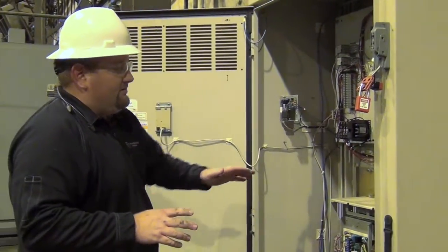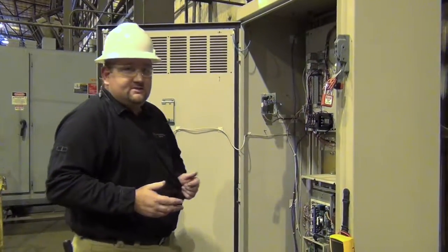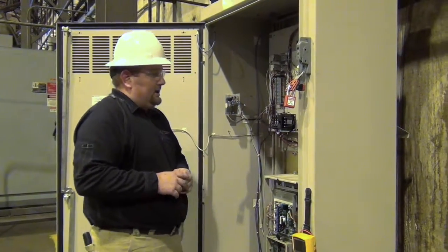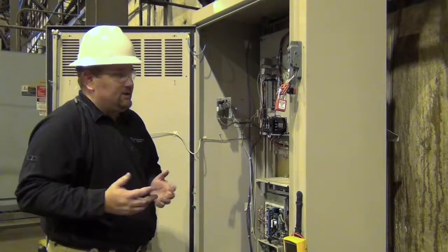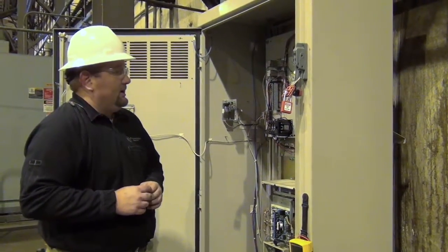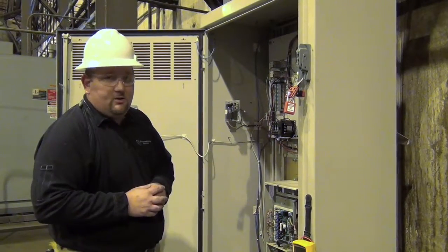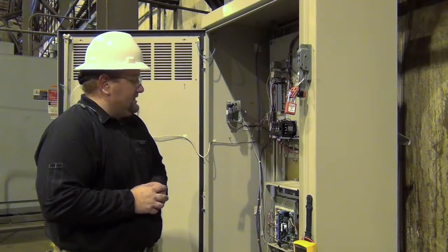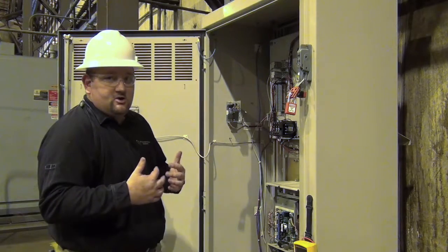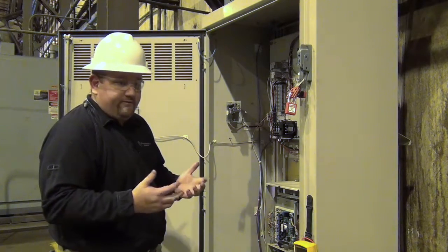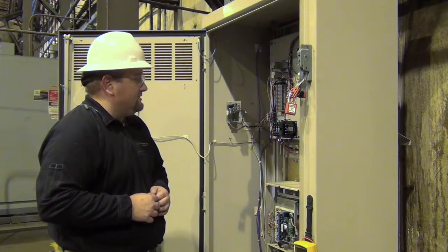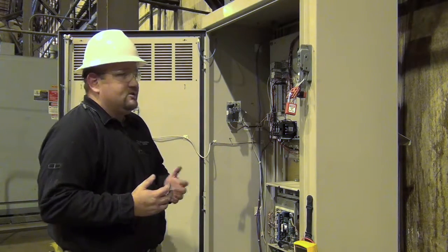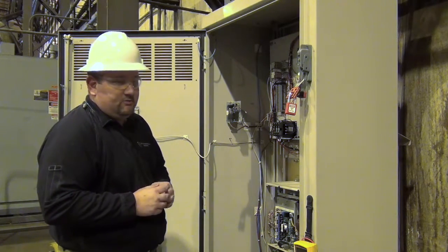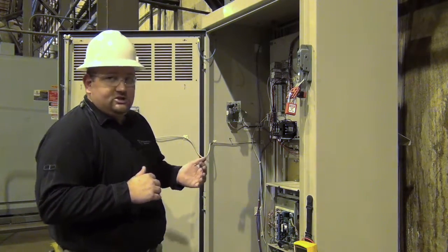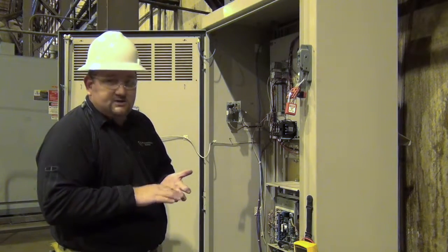Vacuumed the entire cabinet out. This particular drive is actually in really good shape. Sometimes if the drive hasn't been repaired or maintained in quite a while, it's not uncommon to have some dirt and grime left behind that won't come off with the vacuum or the air compressor. If you encounter that in your piece of equipment, our recommendation would be to lightly brush it off with a rag or something.